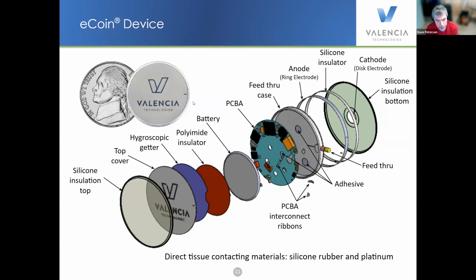We weld the top of the can on. Then we weld on the platinum ring. We weld on the cathode, the disc electrode, and then over that goes the silicone insulation. So there's an overmolding process. And that silicone insulation not only isolates the electricity to go through the platinum disc electrode, but it also provides a kind of soft layer of compliance that's comfortable for the patient. So if you pick up one of these, they feel kind of soft, even though they're a coin, they're not as hard and rigid. And what you have in direct contact with tissue is silicone, rubber, and platinum.